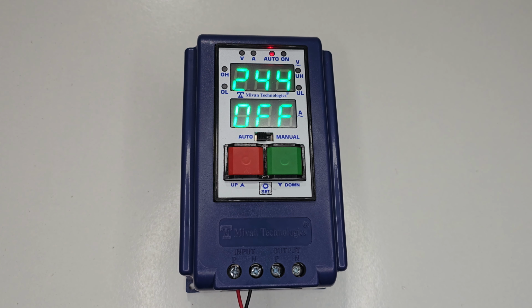That means if you have set a cyclic on timer as 1 hour and cyclic off timer as 2 hour, the water controlling function works in 1 hour, whatever you have set as cyclic on timer. So when the water level gets down, it will start the motor during this 1 hour, and when the water level reaches the stop sensor, it will stop the motor in that 1 hour. After 1 hour, when the cyclic off time comes, the unit will not start, even if there is no water in the upper head tank. So basically, complete water controlling function works in 1 hour only, whatever you have set as cyclic on timing. This is a cyclic timer with water level controller.